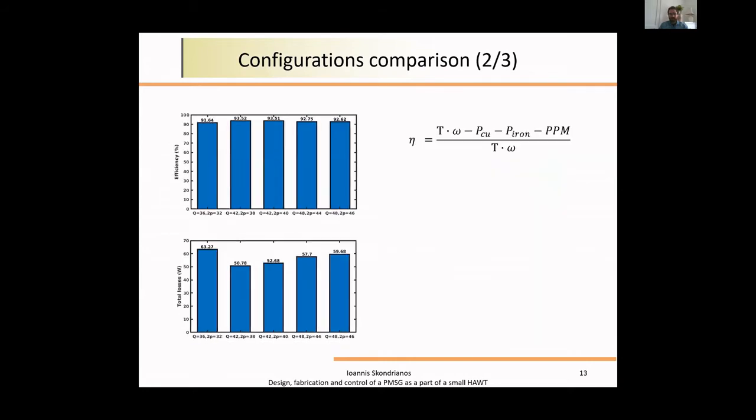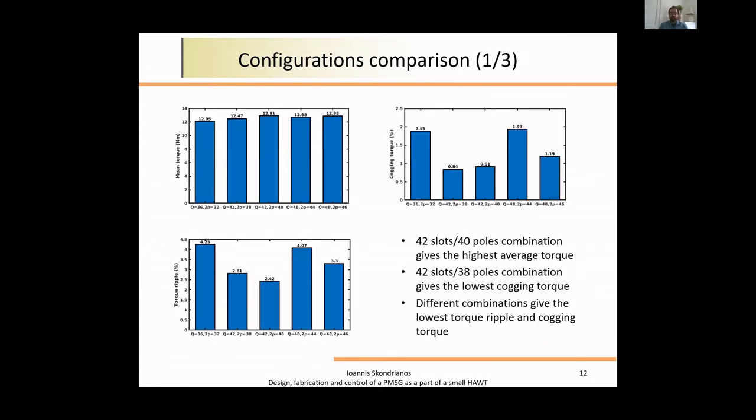In terms of total torque, more or less they give the same results. However, we can see at the top right that cogging torque is much better, much less in combinations of 42 slots 38 poles and 42 slots 40 poles. At the bottom left, the combination with 42 slots and 40 poles gives the least torque ripple. Less torque ripple means less noise while operating and better curves in terms of back EMF.